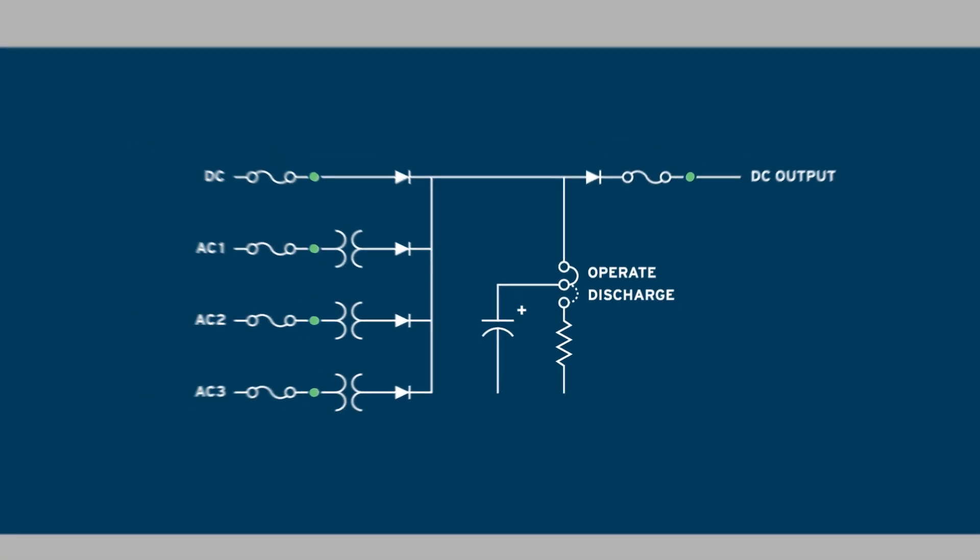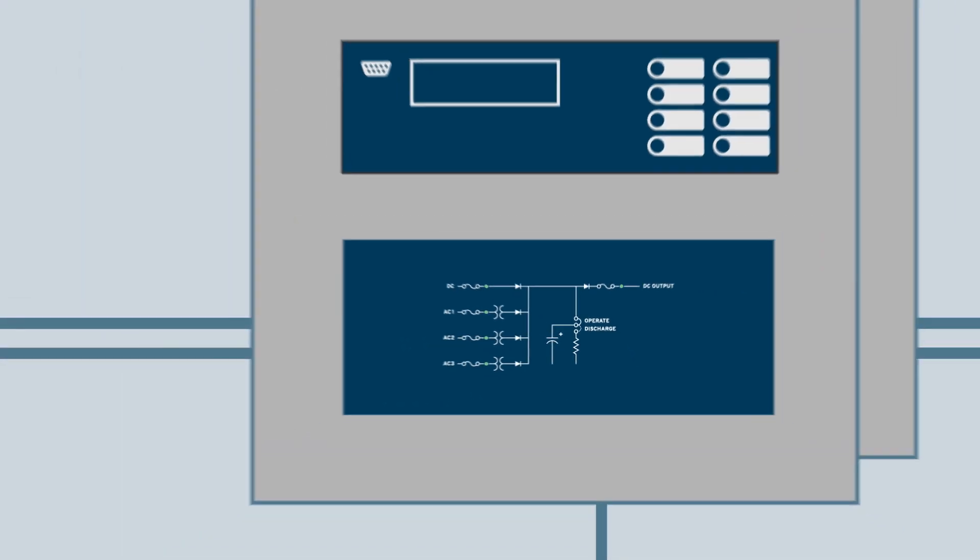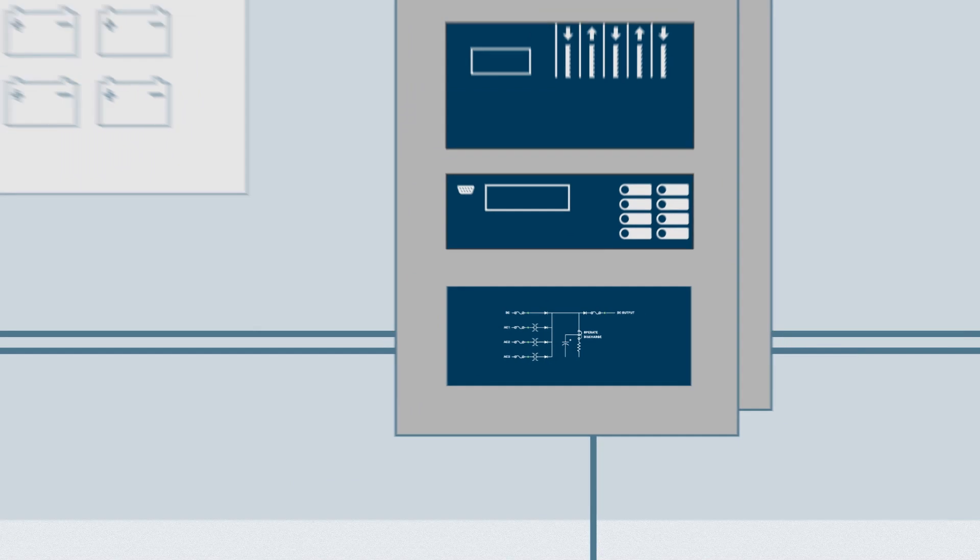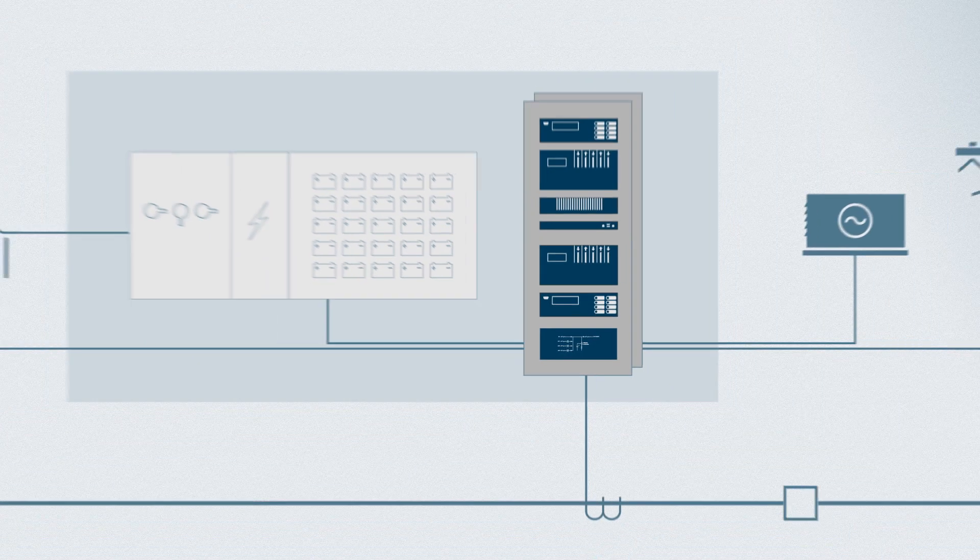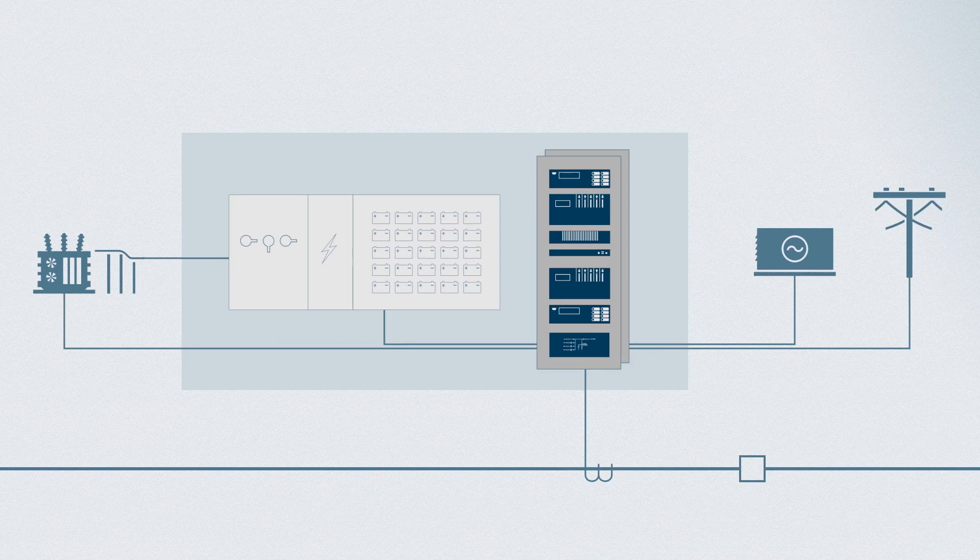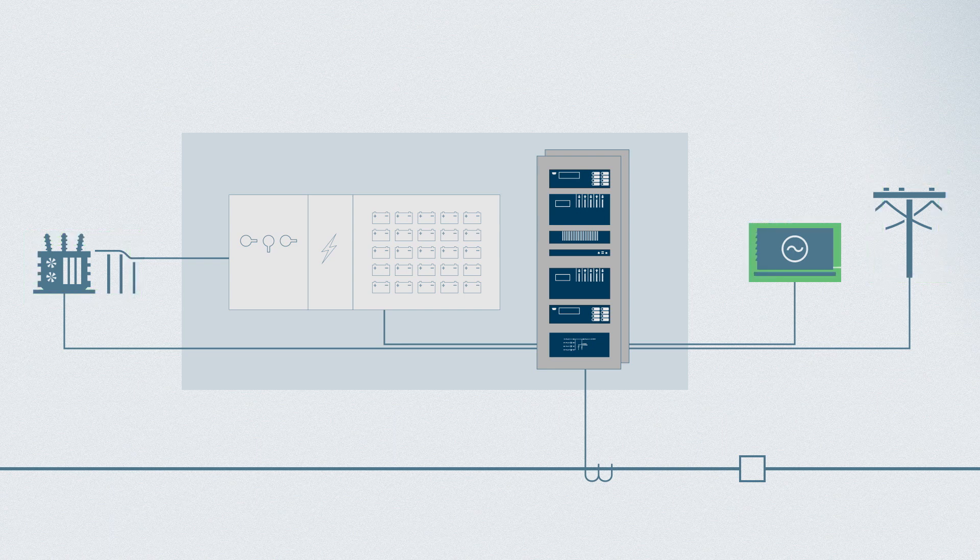You can connect as many as three AC sources to the redundant power module for power supply redundancy and source diversity. Auxiliary sources can come from instrument transformers, station service, or on-site backup generators.